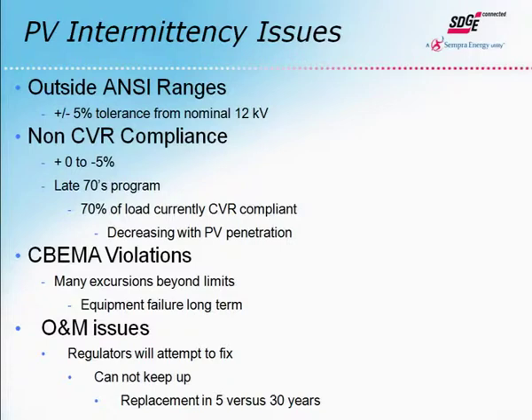So here's the challenges, here's why for utility. You can see here we talk about being outside these operating ranges. One of these is non-CVR, CVR here is a program called conservation voltage reduction. People call these green circuits. People lower the operating voltage at your meter such that you can now actually consume less energy. We have a program in California. We've had it since the late 70s. Roughly 70% of our load is CVR compliant today. What does that mean? Instead of a plus minus 5% range, we're now talking a 0 to minus 5% range. But as the penetration level of PV goes up, we're seeing our ability to maintain that voltage becoming much more difficult.